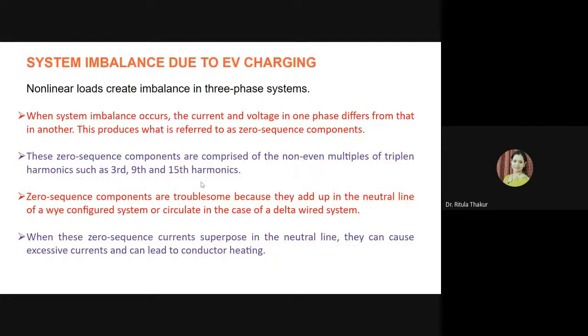Now in those figures, we have seen that because of the imbalance, zero sequence components will appear. These zero sequence components, which mainly comprise the third, ninth, and 15th harmonics, will be troublesome, because in a star connected system they will add up in the neutral line, and in a delta winding they will just circulate. If they are superimposed in the neutral line, they will cause excessive currents that can lead to conductor heating and ultimately to catastrophic failure in the distribution assets.